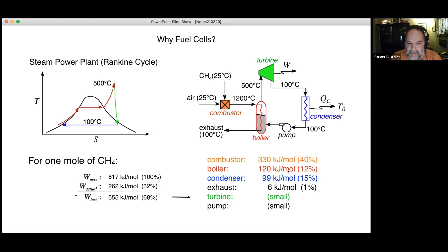The other bigger actors is heat exchange. So the boilers, the condensers, any kind of delta T that you have in your heat exchange equipment, that is going to incur fairly large exergy losses as well. So roughly, maybe another 30% is lost due to the heat exchange processes. So roughly speaking, a third is lost in combustion, a third is lost in heat exchange, and then you have some other ancillary things. Efficiency of the turbine engine, efficiency of the pump, the rotating equipment, those kinds of things, not an issue, like for the most part. So it's not like we can engineer a more efficient turbine engine or engineer a more efficient pump or something that's not really going to help us very much. It's the delta T's that we have, and it's the combustion.